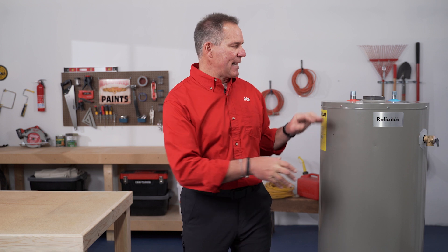The next thing to look at when choosing a tank water heater is the BTUs — meaning how big the burner is. There's standard and what they call high recovery. A standard 40-gallon heater is somewhere around 40,000 to 50,000 BTUs. When you get into high recovery, those numbers are in the 60,000 to 70,000 range, meaning it will heat the water faster and reach the recovery point sooner. That is something very important.